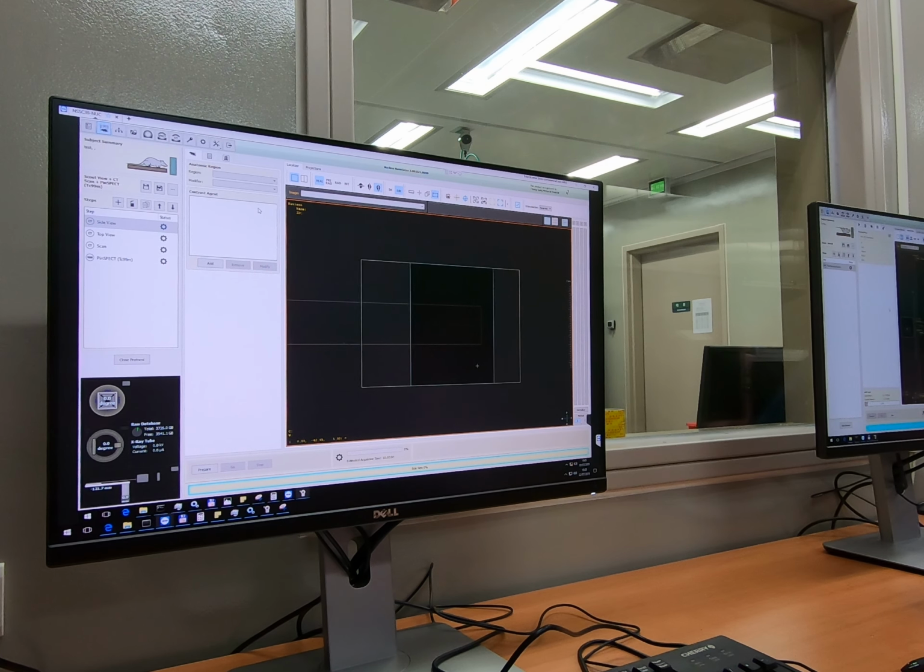So the first one is actually optional, so you don't need to select the region and the modifier. Yeah, it's not even active. And if you don't use the contrast agent, you don't need to add anything here, but there is a list available. There is a kind of fast list which can be configured later with an editor, but there is another extended list with different contrast agents. Sometimes you might need to select some of them. You can also add all the parameters regarding this injection.